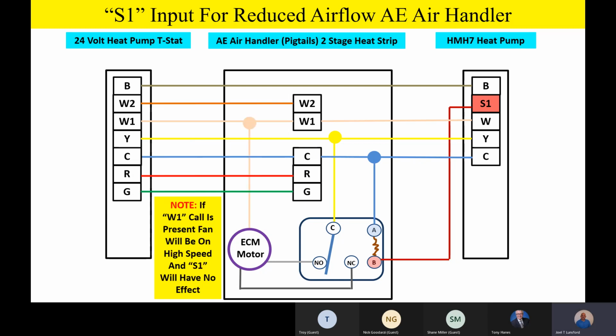You'll notice that in this example, I went ahead and put the W1 wire back in. So if you do have a W1 call, even if you're in reduced airflow, remember we're going to energize the number 5 speed tap on that ECM motor with an auxiliary heat call or a defrost call, and the fan will go up to a higher airflow. Another way to think about it is that even if we have an S1 input from the outdoor unit and we call for auxiliary heat, that ECM motor is always designed so that if it has more than one command, let's say we have a 60% airflow command, then all of a sudden, bang, we have an auxiliary heat command, it's always going to take the highest of the commands it's receiving. So if that ECM motor has 2 or 3 commands for different speeds, it'll automatically take the highest speed that it's commanded. That's called airflow priority.